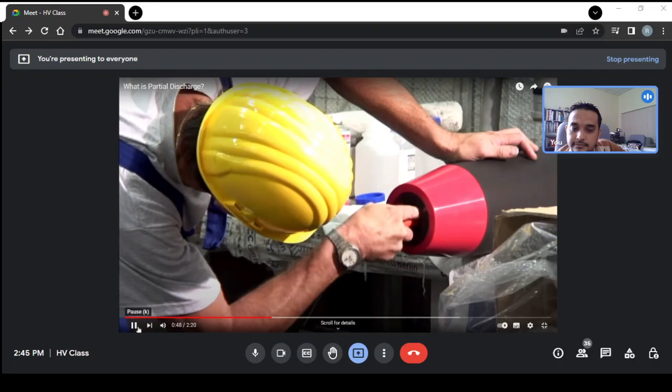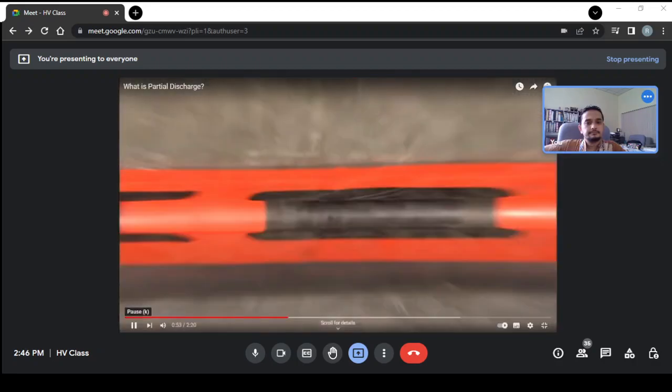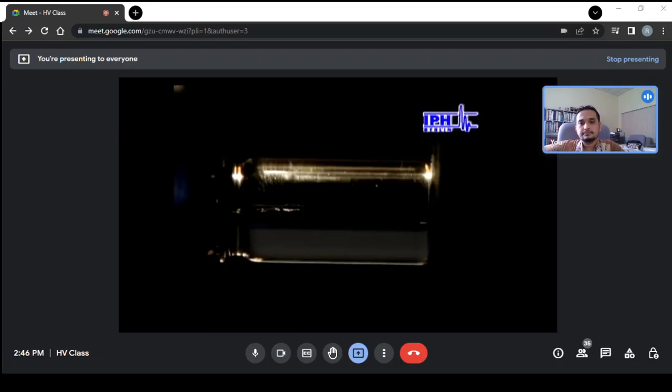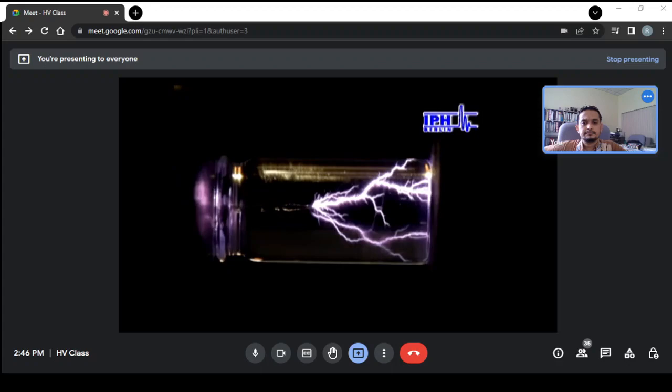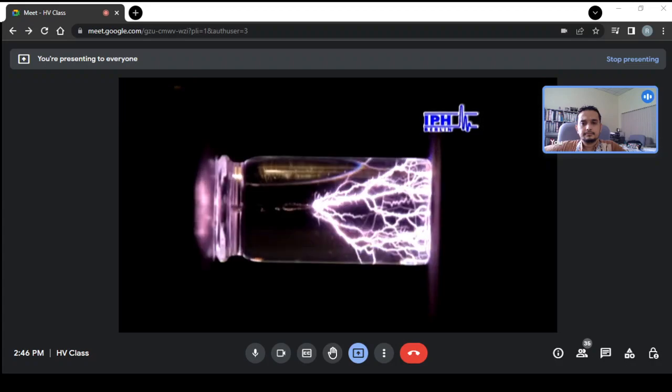A partial discharge, or PD, is a localized dielectric breakdown of a small portion of the electrical insulation. It can be initiated by voids, cracks, or inclusions within a solid dielectric, at interfaces within solid or liquid dielectrics, in bubbles within liquid dielectrics, or along the boundary between different insulation materials. PD causes the insulation to deteriorate progressively and can lead to electrical breakdown.